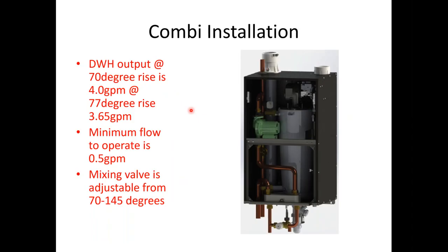So, I said at the beginning we were going to talk about the combi. Again, we only have one size on the combi. It's going to be 155,000 BTUs. Roughly, it gives us 4.5 gallons a minute at a 70 degree rise, and it takes a minimum of a half gallon a minute to operate it. The mixing valve comes included with it. The piping down here is already included with it, with the mechanical flow switch.